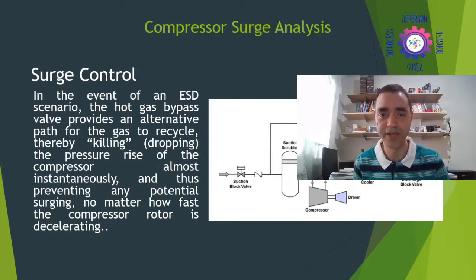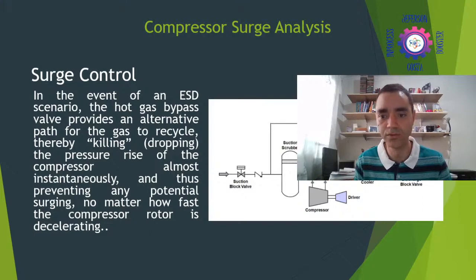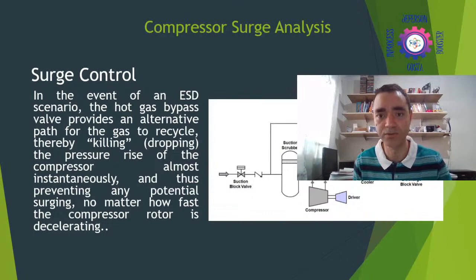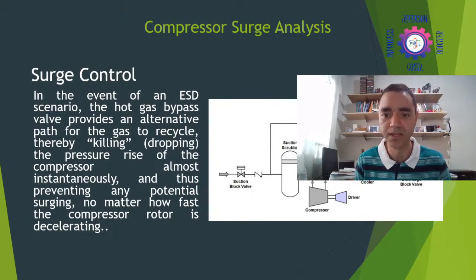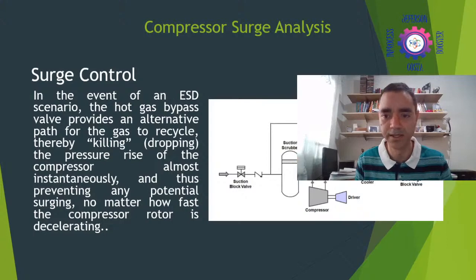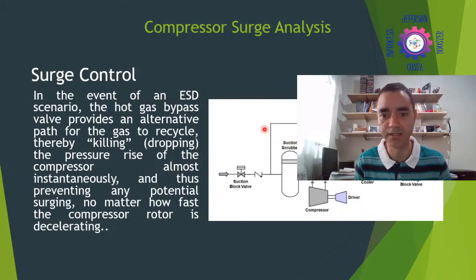Eventually the anti-surge valve alone is not enough — it may not deliver a fast enough response for a large compressor. In that case, you can consider a hot gas valve, which guarantees a faster response to avoid surge conditions. The hot gas valve will not be the same size as the anti-surge valve — it is only to boost your surge control. A rule of thumb is that the hot gas valve is 50% of the design flow. This is what I will record for my training program students — how to evaluate it and specify this valve in plant design.